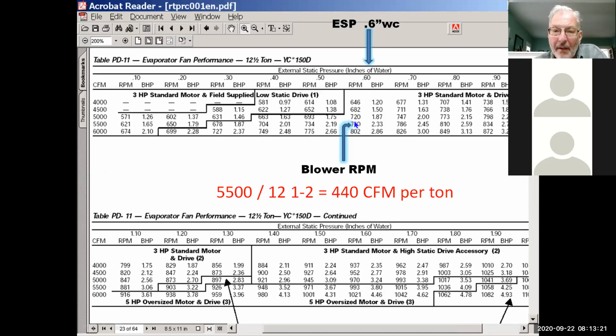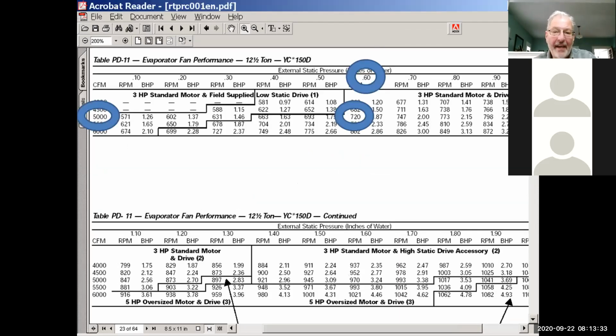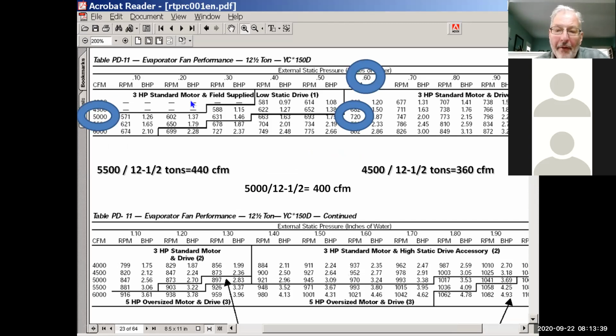It gives us our static pressure. If we know our static pressure, we can look at our RPM. Our RPM tells us what the CFM is on that unit. So this is what we just talked about: if I want to get to that 5,000 CFM, I have to be down to 720 RPM. And again, if I wanted to go to 360 per ton, I'd go down to the 682. So that's basically what this chart's telling us: what's our static pressure, what's our RPM, and that gives us our delivered airflow.